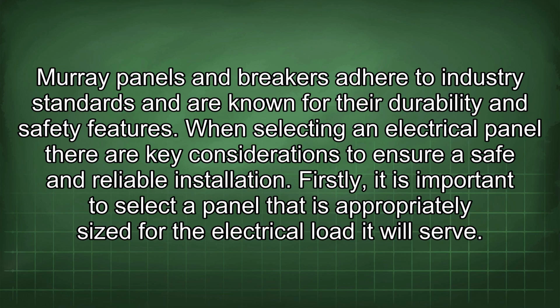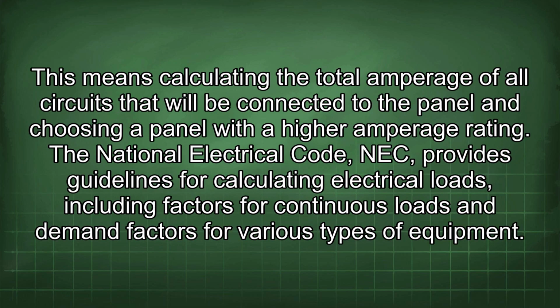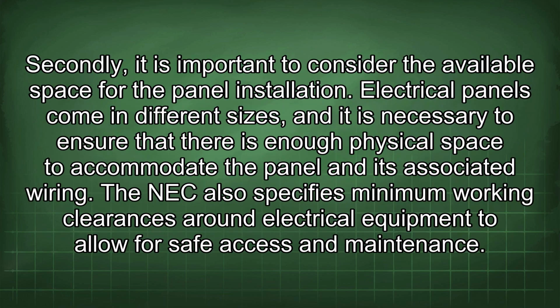When selecting an electrical panel, there are key considerations to ensure a safe and reliable installation. Firstly, it is important to select a panel that is appropriately sized for the electrical load it will serve. This means calculating the total amperage of all circuits that will be connected to the panel and choosing a panel with a higher amperage rating. The National Electrical Code (NEC) provides guidelines for calculating electrical loads, including factors for continuous loads and demand factors for various types of equipment. Secondly, it is important to consider the available space for the panel installation. Electrical panels come in different sizes, and it is necessary to ensure that there is enough physical space to accommodate the panel and its associated wiring. The NEC also specifies minimum working clearances around electrical equipment to allow for safe access and maintenance.